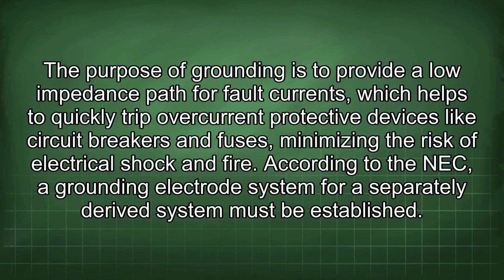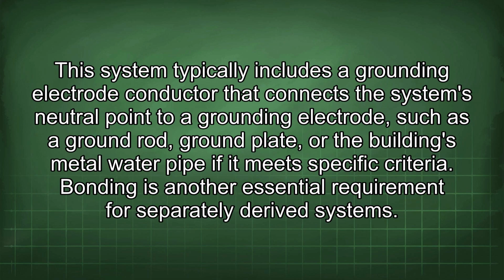According to the NEC, a grounding electrode system for a separately derived system must be established. This system typically includes a grounding electrode conductor that connects the system's neutral point to a grounding electrode, such as a ground rod, ground plate, or the building's metal water pipe if it meets specific criteria.